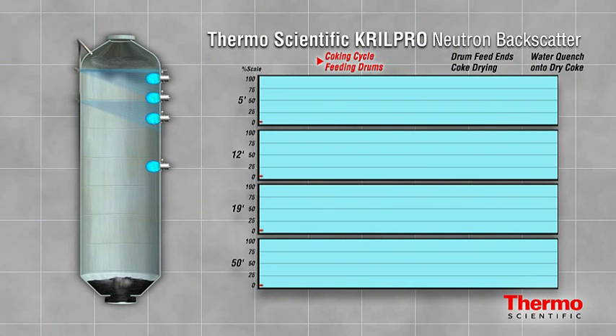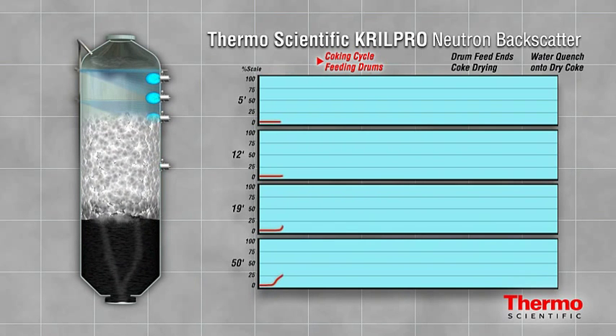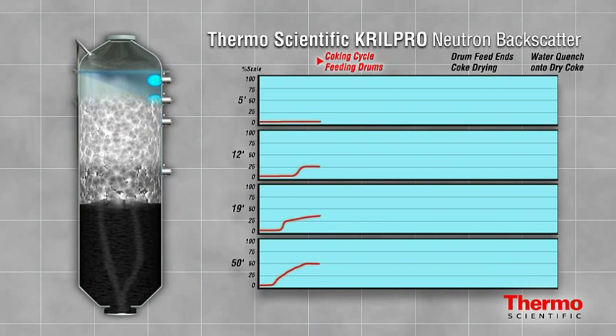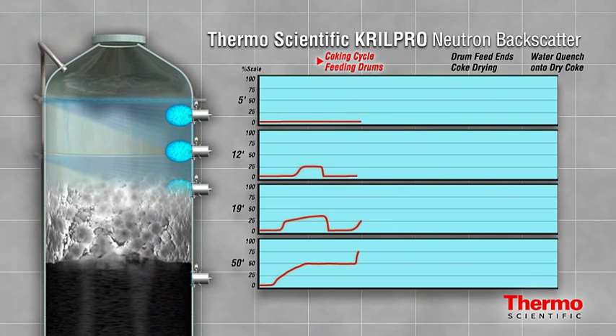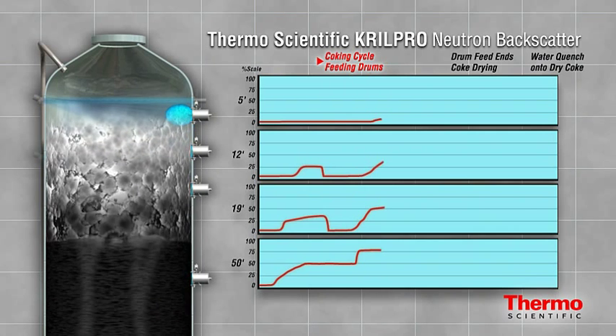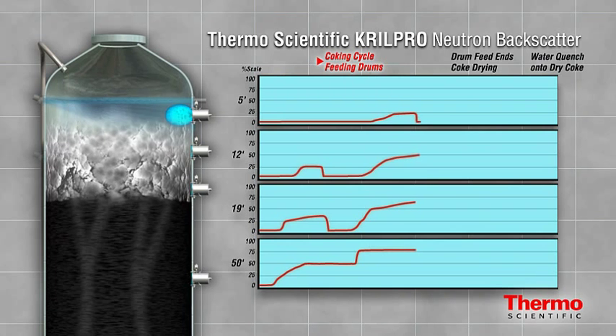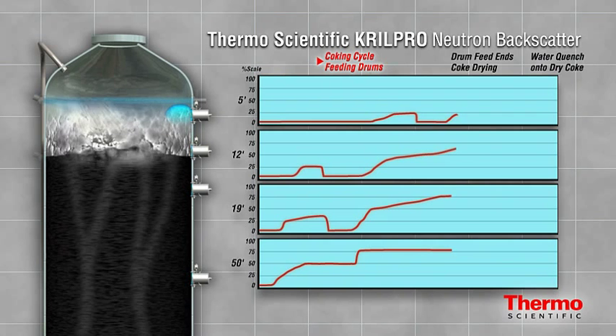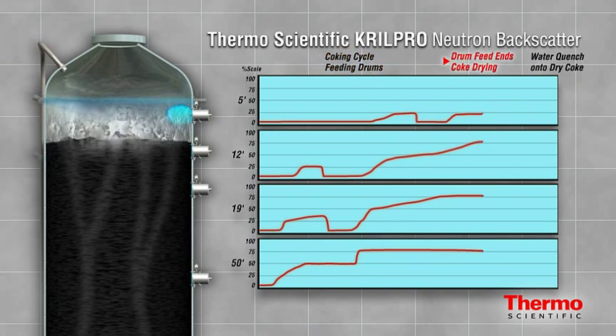By observing this output, operators know the density and type of material present at each point in the drum. During each stage of the coking cycle, process conditions must be continuously monitored. The charts represent Thermo Scientific KRILPRO neutron backscatter technology in action. As the drum fills, the coke and foam rise independently and at differing speeds. The KRILPRO indicates the density of the material at various levels, including wet and dry coke, as well as light, medium, and heavy foam.